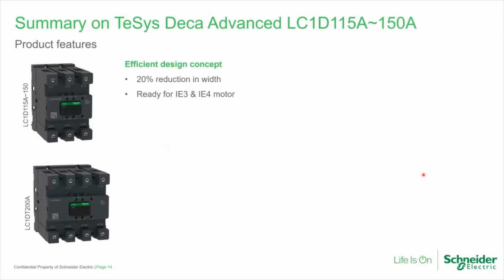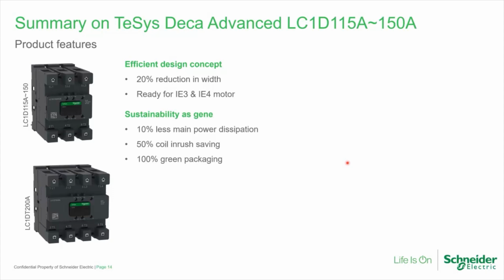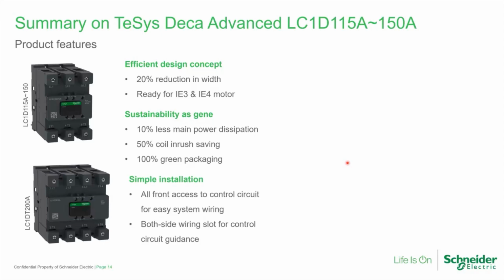If I have to quickly summarize all the product features, I can say that the width of this contactor has been reduced by 20%. This contactor has been tested for I3 and I4 motors, and hence we call this AC3E. This is more sustainable because it has an electronic coil, and this electronic coil helps us achieve a 50% reduction in inrush current. Similarly, there's one more patent associated with this. The power poles are again patented for this contactor, and hence you can see there can be 10% less power dissipation while using this contactor.